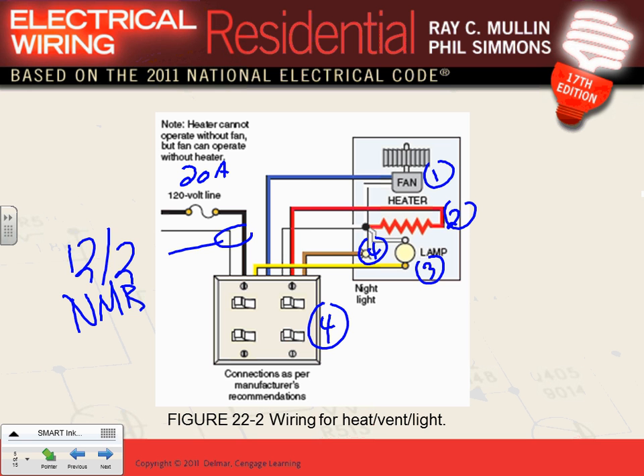Now, can you guys look at this and tell me how many wires I need to make the system work? I need 1, 2, 3, 4, 5. 5 wires, 5 conductors. Now, how would you get a 5 conductor NM cable? Plus the ground. There is no 5 conductor NM cable. So how would you wire this? From here, it's a 12-2 NM cable, no problem. The rest of them, you're going to use typically flex.